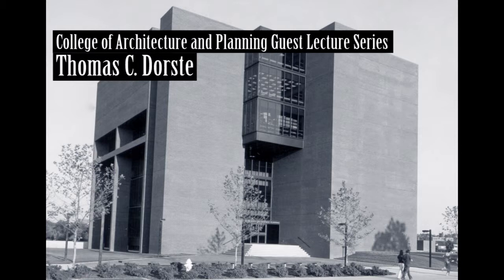This means that once adjusted properly, and that took a little time, the only thing needed besides that is cooling on the interior space and possibly cooling in part of the perimeter, which was on the heated side. So this boils down to the fact that the building has a variable volume system that takes care of 80%, which has a cooling coil in it and no heating coil. There's no heating coil in the system at all. The normal load in the building will require cooling in the center section. It will also introduce cooling in the perimeter section when this is required.